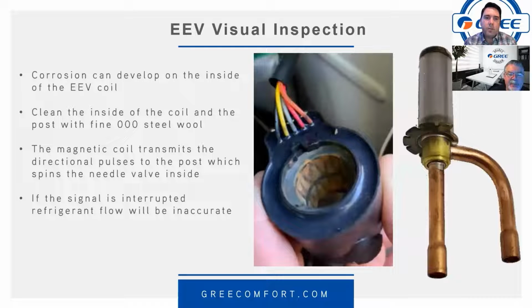Another thing that can happen, and this is an easy visual inspection, pull that coil off and just take a look inside. Corrosion can develop over time on the inside of the EEV coil, and environment has a lot to do with it. If you're in a cold, wet environment, or I guess even some condensation and things like that can be problematic. So clean the inside of this thing. If you see it dirty like that, clean it with some fine 000 steel wool. Clean the post as well.